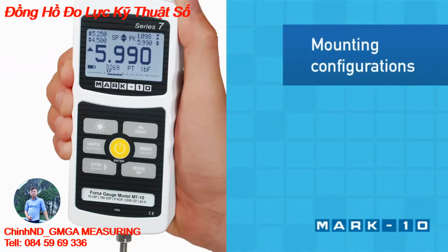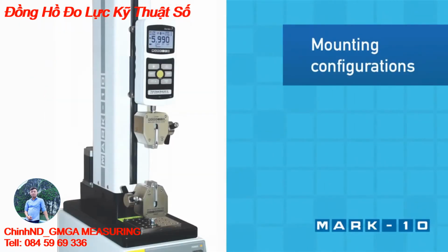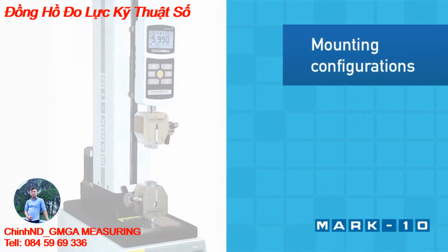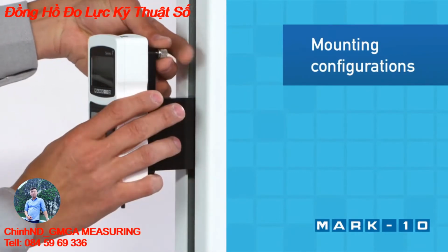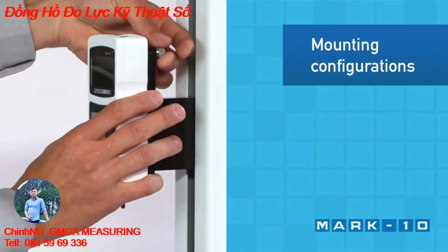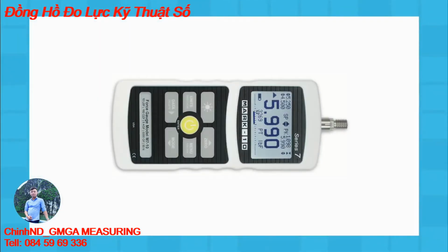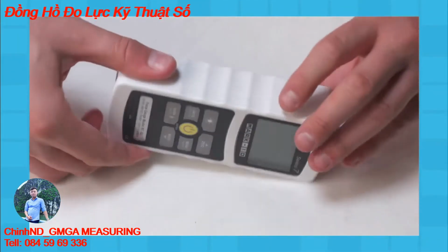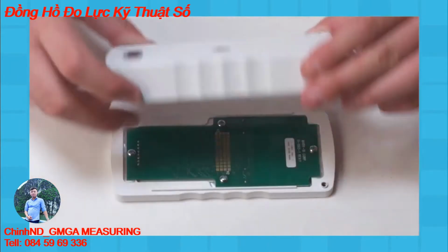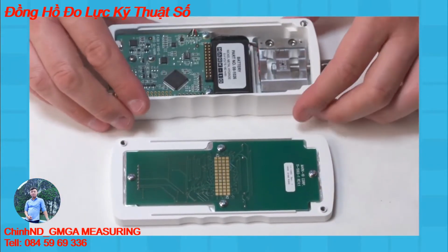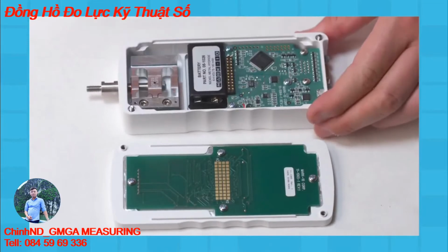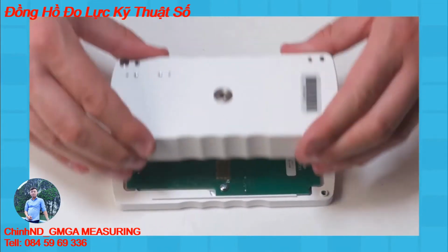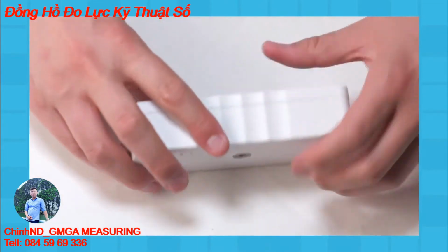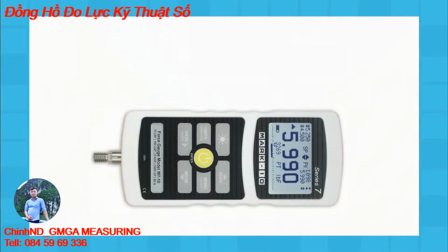Use the force gauge handheld or mount to a test stand for more controlled testing. Match the hole in the rear of the housing with the dowel pin located on the test stand's mounting plate. To accommodate handheld or test stand mounting, the orientation of the load cell shaft may be flipped while the keypad and display remain upright. To reverse the orientation, separate the 2 halves of the housing, reverse, and reassemble.